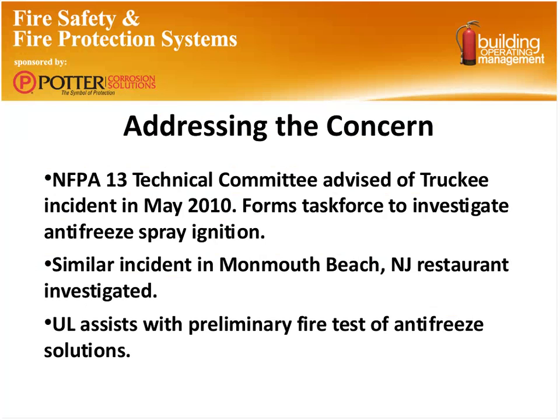And when that discharge hit the heater, again, it responded with a fire, and actually that antifreeze, being super atomized, created not really an explosion because it wasn't confined, but did aggravate the fire and cause a problem. Ultimately, the sprinkler systems do typically put these fires out.